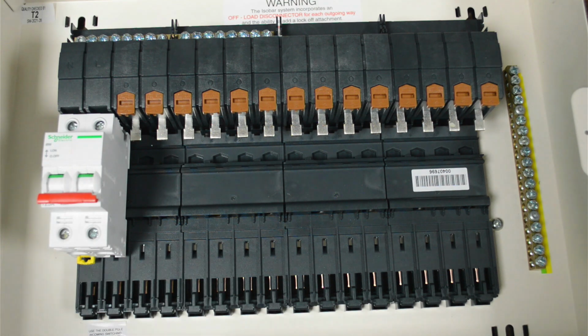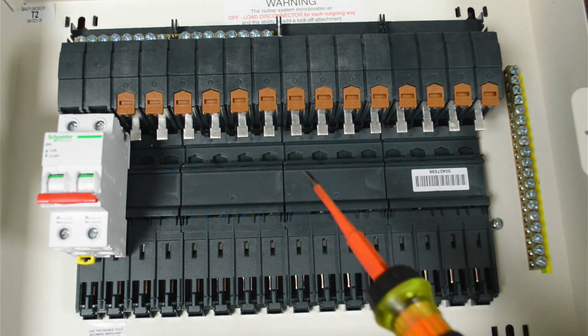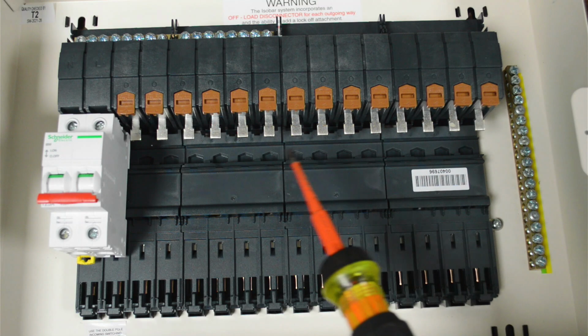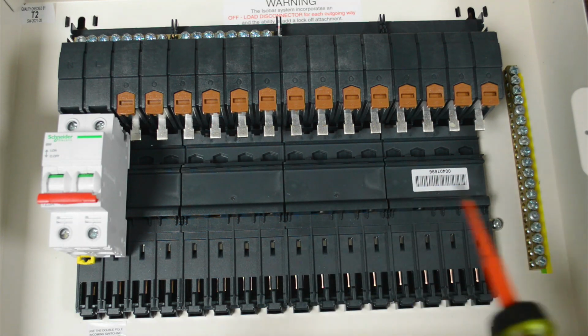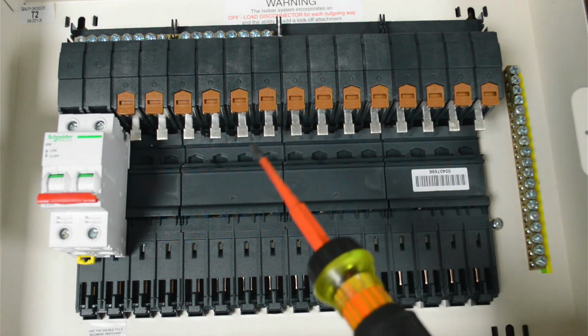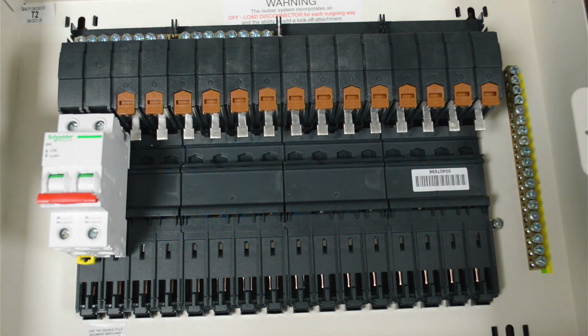I don't want to get into the thick of that at the moment. I just really wanted to talk about some of the key features of this particular board, and you will note that there are the big lugs along here. So these are a pre-installed busbar, if you like, for the live terminals. You will also see here that there's been a main switch installed, and note the N on there for the neutral, and we have the L for the line.